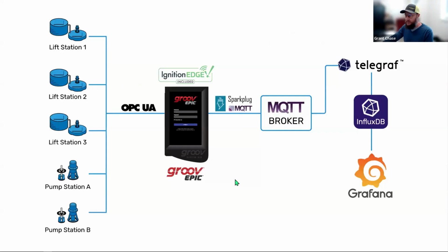We use Influx, SQL, Postgres, many different ones going into Grafana. If you have a larger, more distributed system, you can also take the route of MQTT with different stations. In our case, we do this with our lift stations and pump stations, as well as water, going into a groov EPIC and then transmitting those messages using Ignition Edge and the device drivers using Sparkplug to the broker. And then we ingest that into our database, in a highly scalable way, using MQTT and a broker as that central data hub. So without further ado, I'm going to get into Grafana itself.